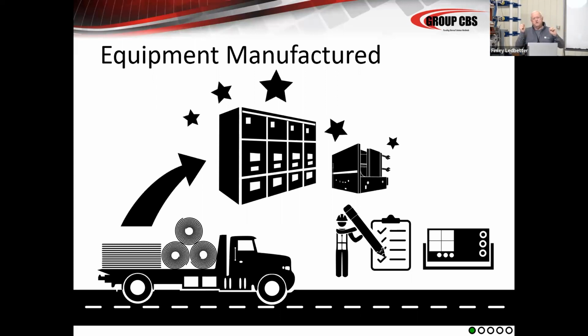The switchgear is assembled, instrument transformers, current transformers, wiring can be very complex, possibly generator or transfer gear, or it can be very simple distribution gear. And then you see a little logo here. You've got a guy doing all kinds of inspections. You've got a certain amount of electrical testing. They'll push current through the control circuits. They'll push current through the trip circuits. They'll finger the protective devices. They'll open and close the breakers. They'll push three-phase current and make sure all the metering indication and all the relaying works. They have tests for all this at the plant. So the switchgear is tested pretty thoroughly.